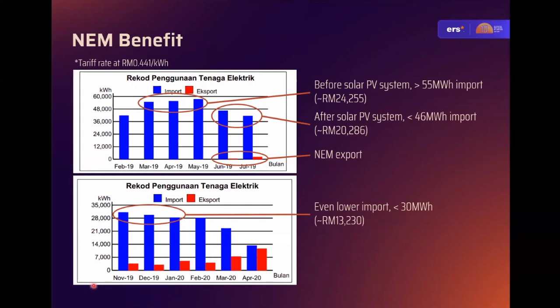Fast forward to November, December, January of this year, you can see an even lower import of kilowatt hours, less than 30 megawatt hours, about 13,000 ringgit Malaysia, which translates to a total of 10,000 ringgit of savings. If we include the NEM export offset, there will be even more savings. During March and April this year, the MCO period, you can see there's a lot of NEM export because of the halt in business and operations. So technically, the bill that you pay is the difference between these two bars.